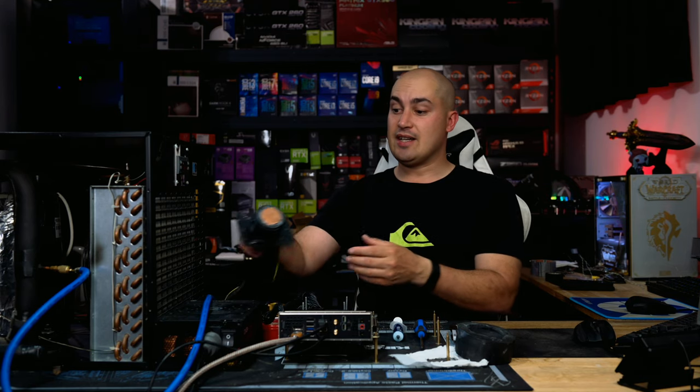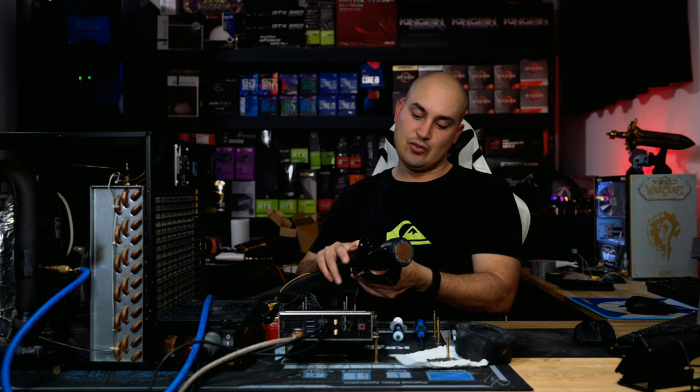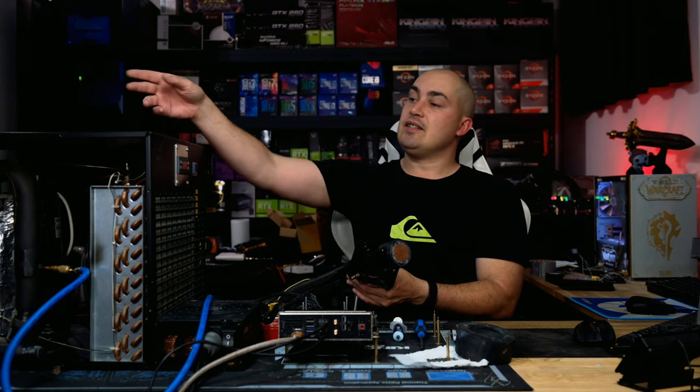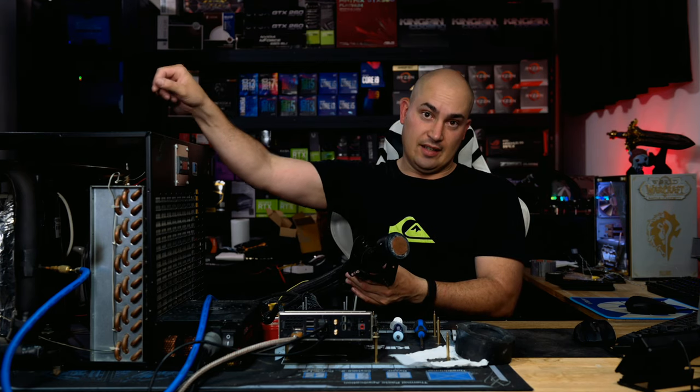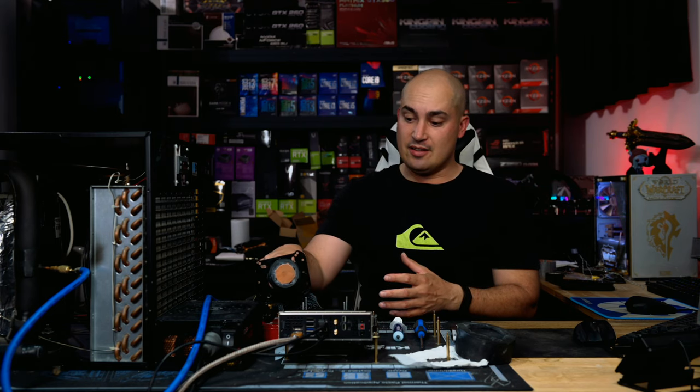Anyway, yesterday I attempted to fix it. There was like a hole in a tube inside the phase change and I had to braze it with soldering and everything, so it took me like five hours to do a proper job. Today I checked and it's leak free, so I don't have any leaks anymore and I recharged it with the gas.